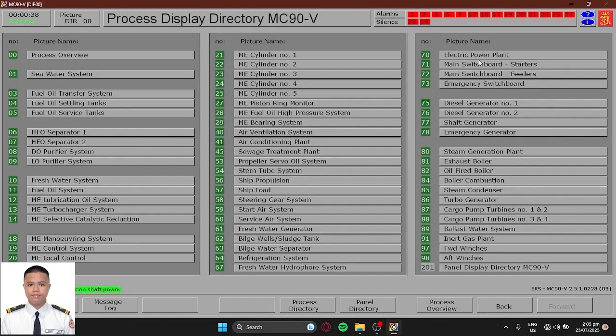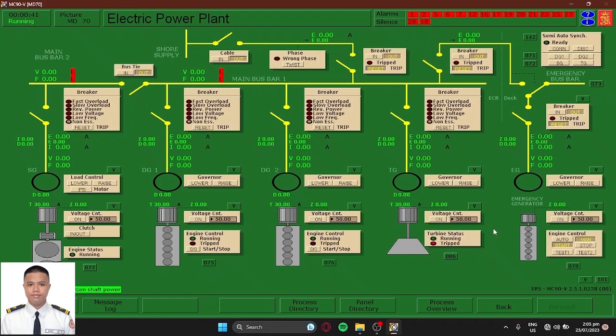Next step is to go here, 70. 70 in process directory is electric power plant. So in this area, emergency generator, turn this voltage control on. Wait for the breaker to turn yellow or this voltage to go 440. There we go, it just turned yellow. Turn this breaker in, turn the bus tie in, and auto the engine control. There we go.